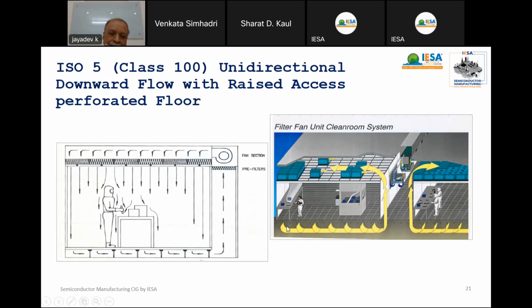The picture: this is a graded flooring, and this is a false ceiling. We have housed a number of FFUs, fan filter units or fan filter modules. So the makeup air required to control temperature and humidity will be sent in between the ceiling and the false ceiling. That air is picked up by fan filter units and circulates through a local return system.